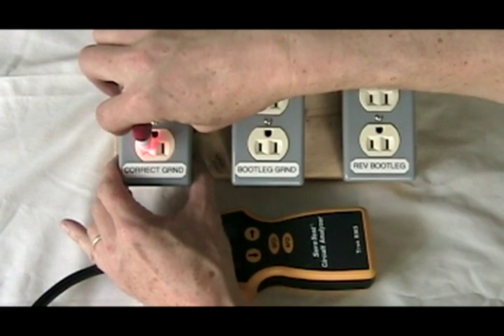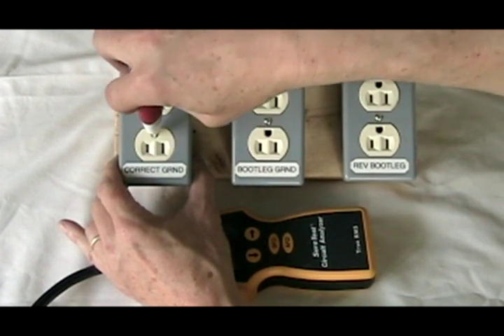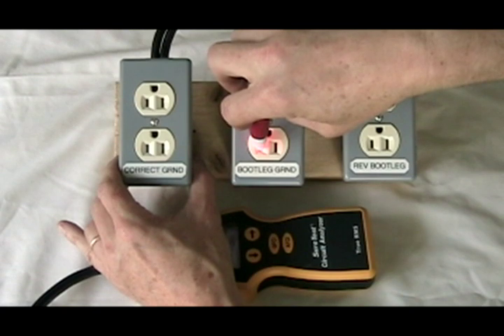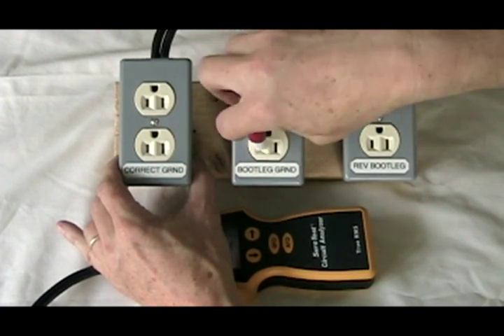On the correctly grounded outlet, the volt probe shows hot, no blinking on neutral, nothing on ground — but hot is hot. On the bootleg ground, it shows the same thing: hot is blinking, nothing on neutral, nothing on ground, hot is good.